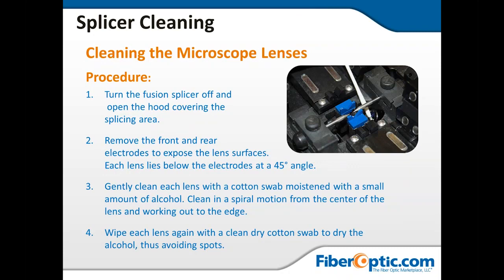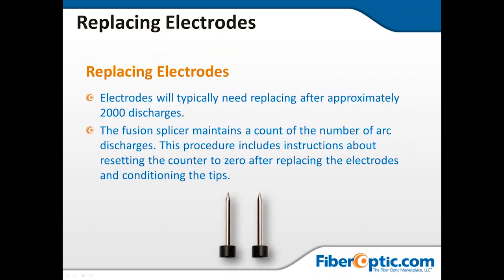Turn off the splicer. Open the hood covering the splice area. Remove the front and rear electrodes to expose the lens surfaces. Each lens lies between the electrodes at a 45-degree angle. Gently clean each lens with a cotton swab moistened with a small amount of alcohol, in a spiral motion from the center of the lens, working out to the edge. Wipe each lens again with a clean, dry cotton swab to dry the alcohol, thus avoiding spots. This is very important.